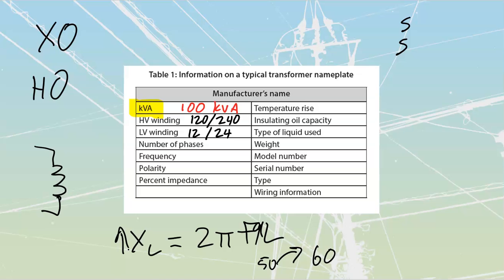For us, operating on a 60 hertz system, if you get a 50 hertz transformer that is sent to you by a piece of equipment that comes from Europe or Asia or something like that, you have to know that that 50 hertz transformer can put out less amps on our system.